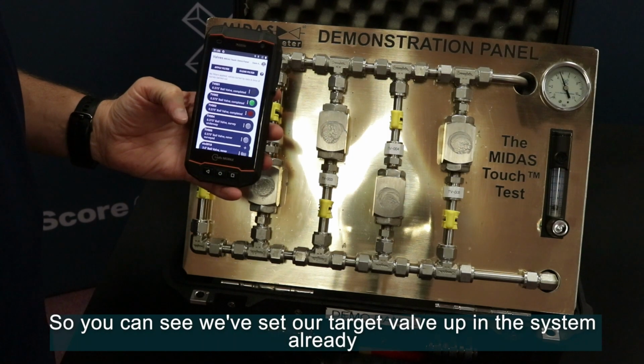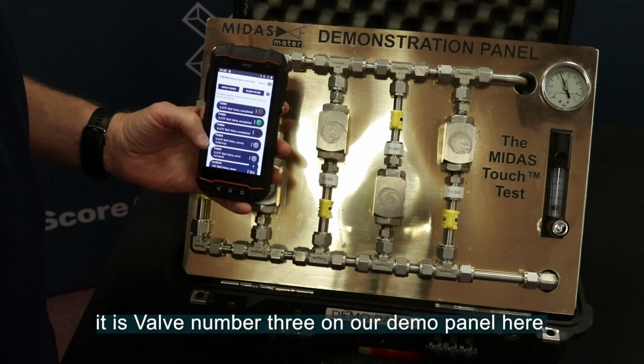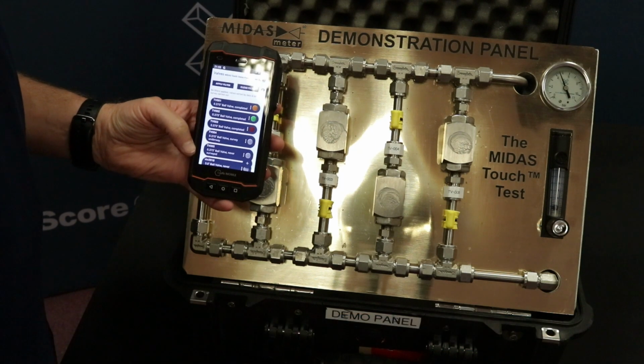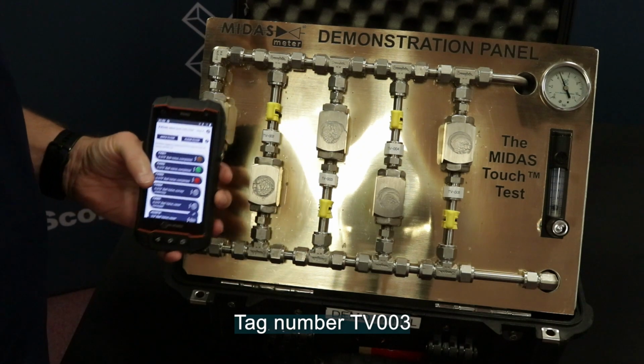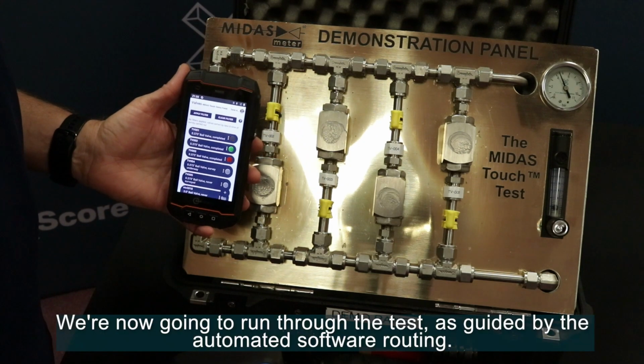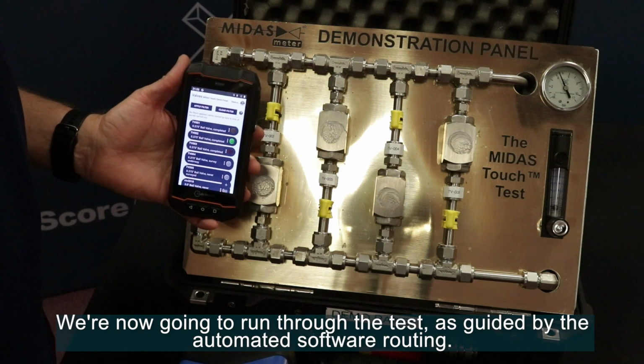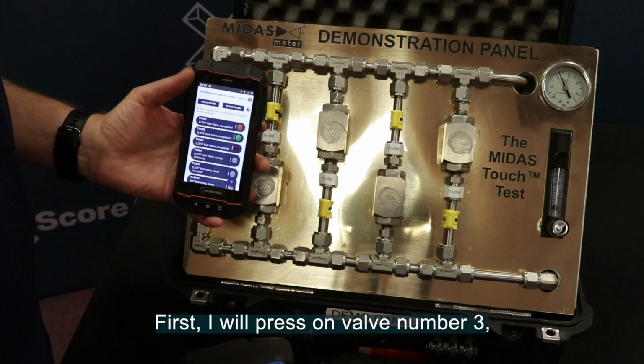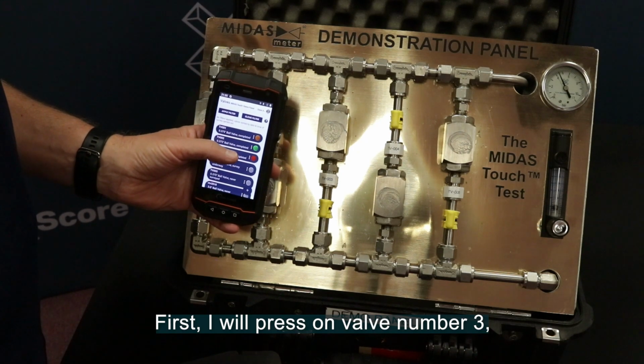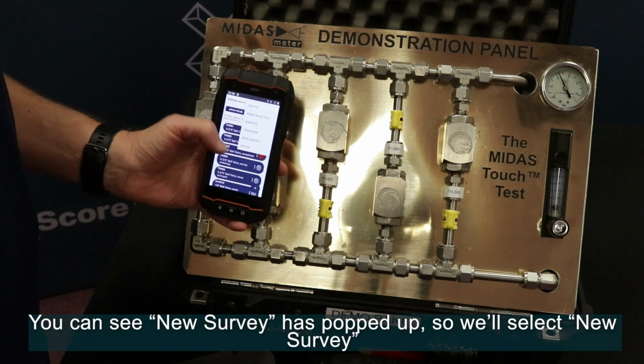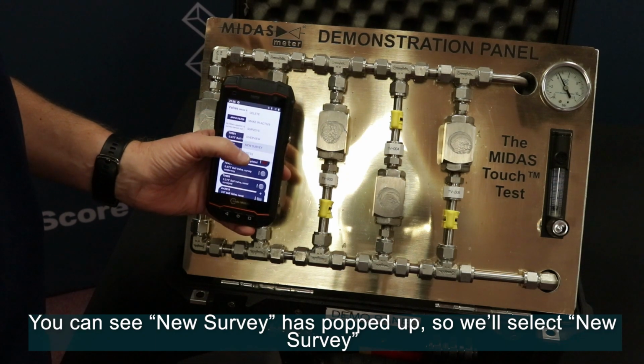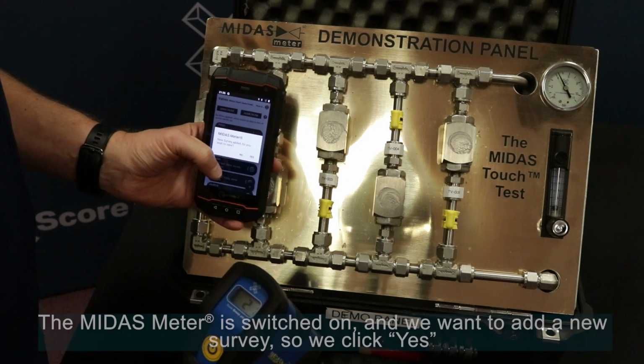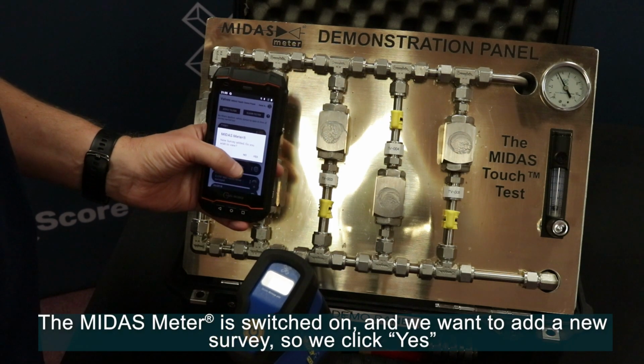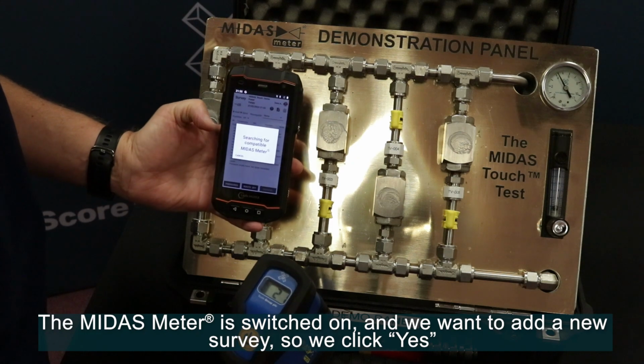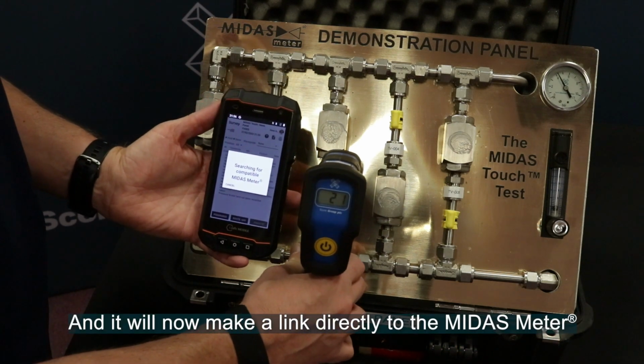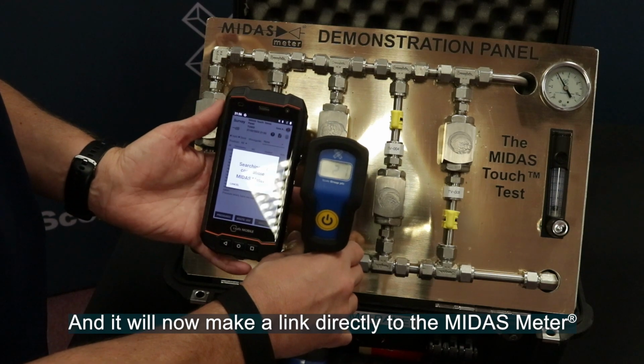So you can see we've set our target valve up in the system already. It's valve number 3 on our demo panel here, tag number TV003. We're now going to run through the test as guided by the automated software routine. First, I will press on valve number 3. You can see new survey has popped up, so we'll select new survey. The MIDAS meter is switched on and we want to add a new survey, so we click yes, and it will now make a link directly to the MIDAS meter.